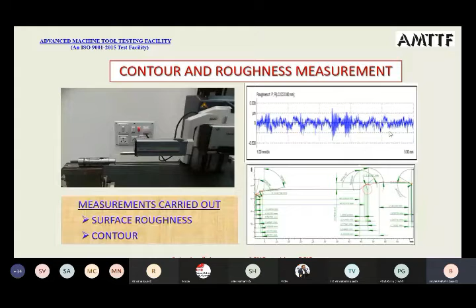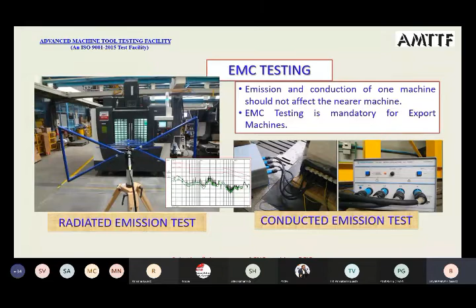One more thing, we have EMC testing. This may not be regularly used by the user—I'm just pointing out the facility available with us. If you have a product being exported from your organization, there is a requirement for EMC testing, and we have the equipment here to check it as per the relevant ISO or EN standards.